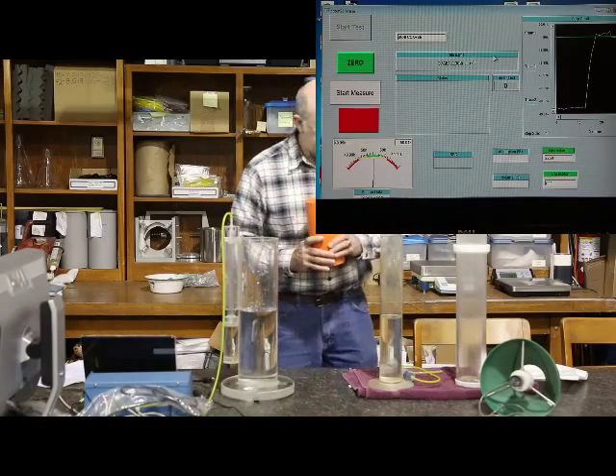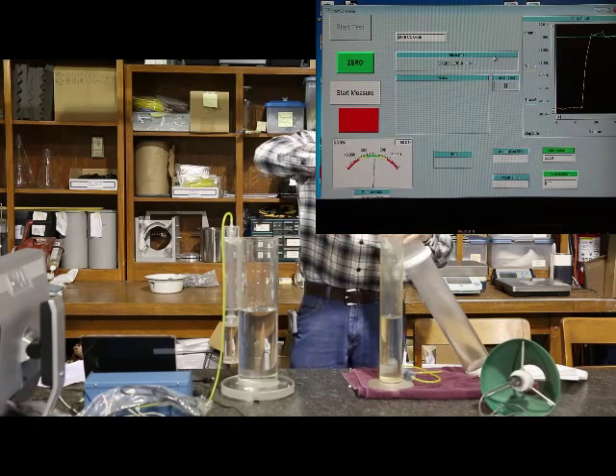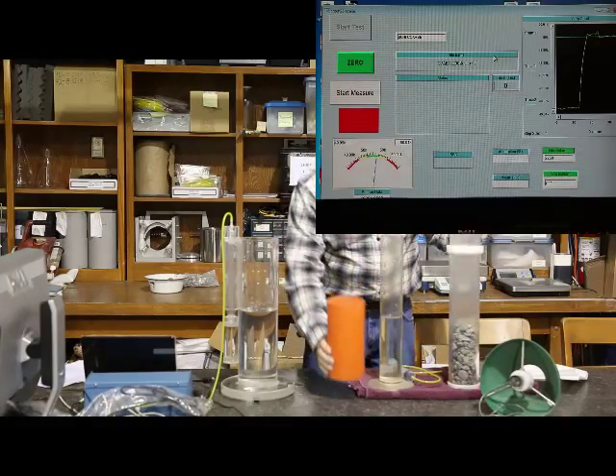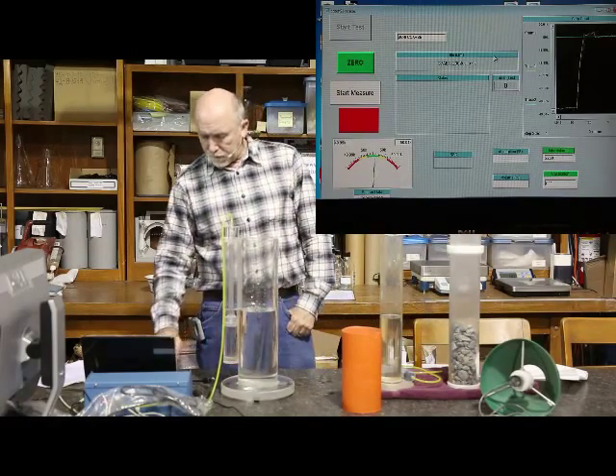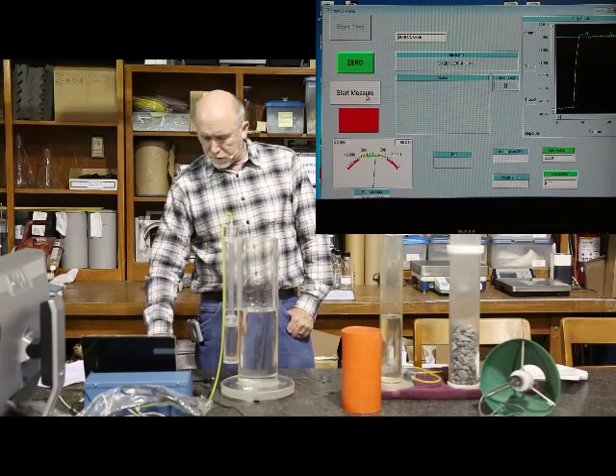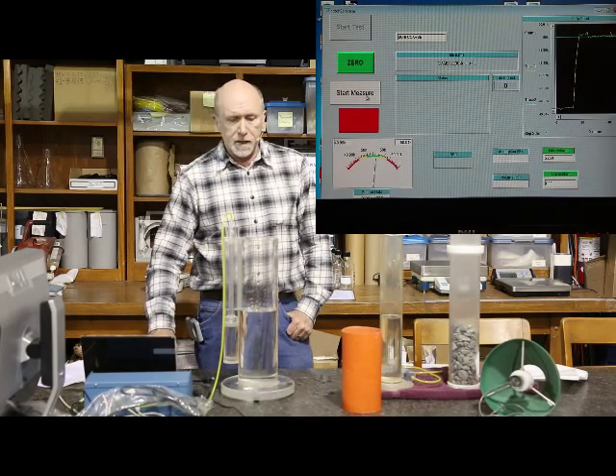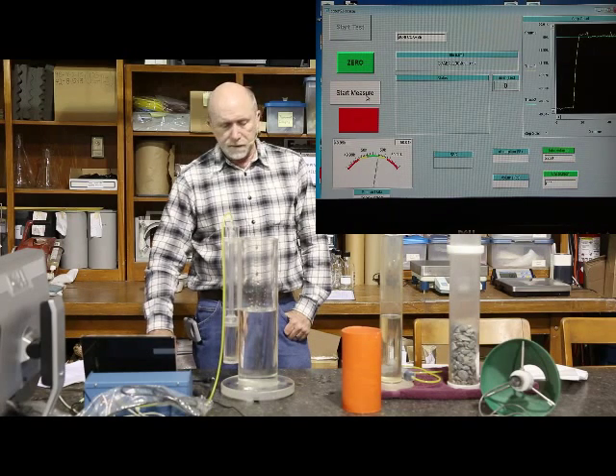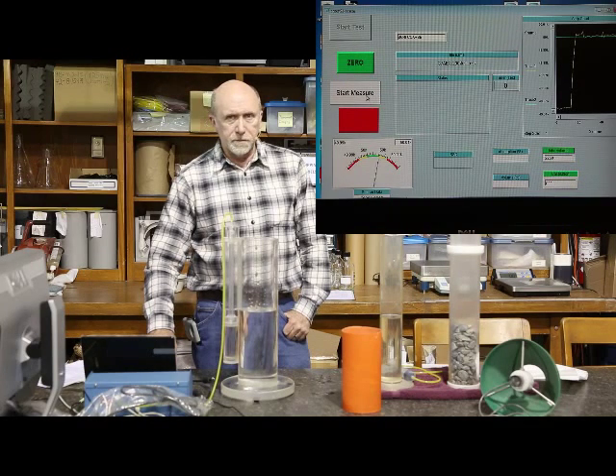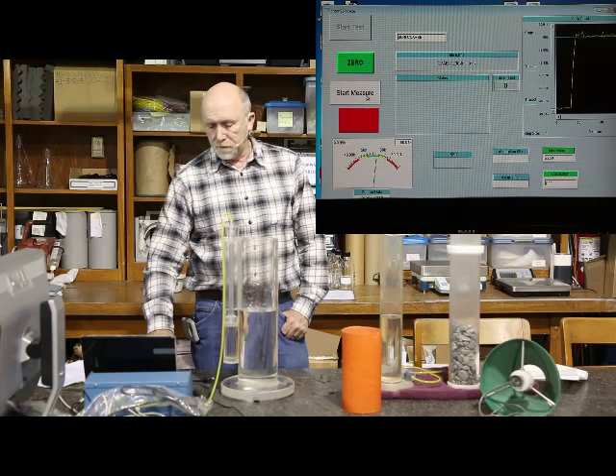Now we're going to take our sample and place it into the sample tube, and we're ready to hit start measure. This will be doing the electronic zeroing. Then the computer's going to tell us that it's time to place this tube in, and we'll have 10 seconds to drop the tube in and oscillate it to release the air pockets, and the computer will then do the measurement.